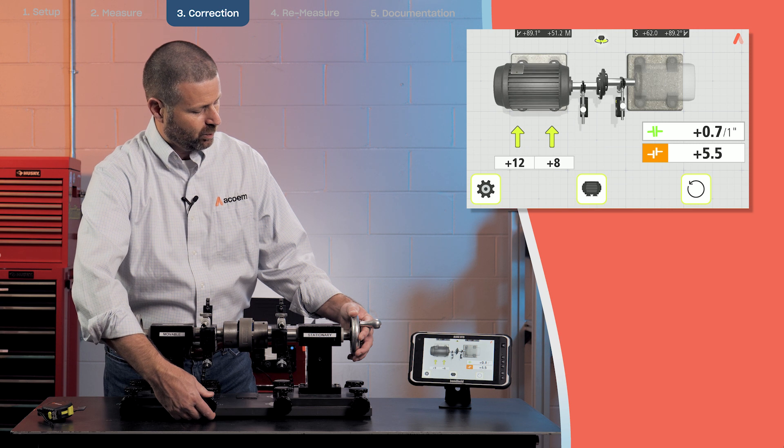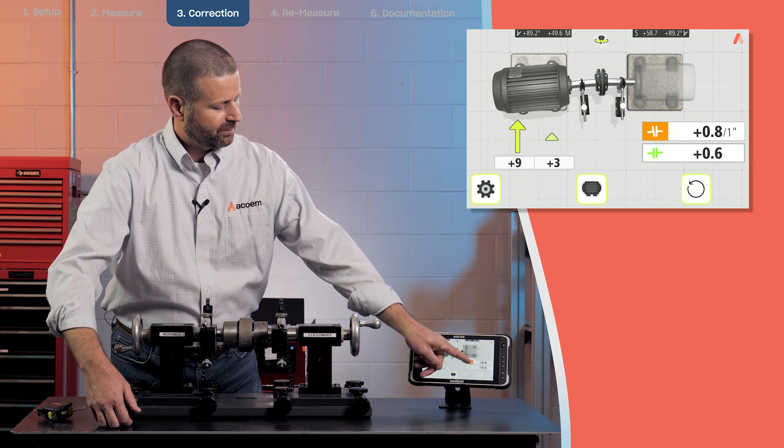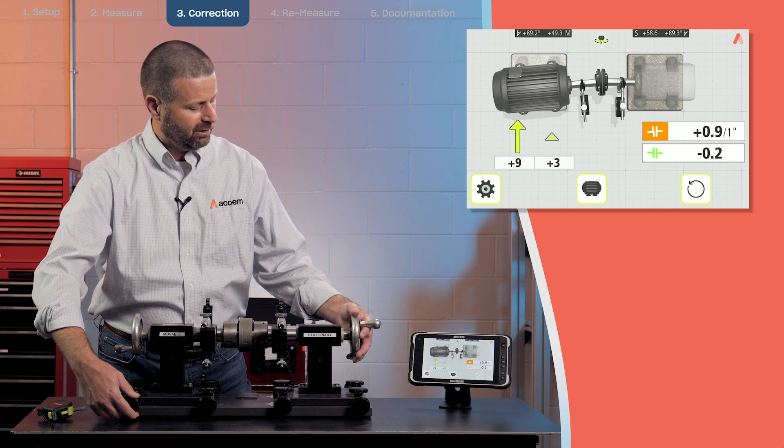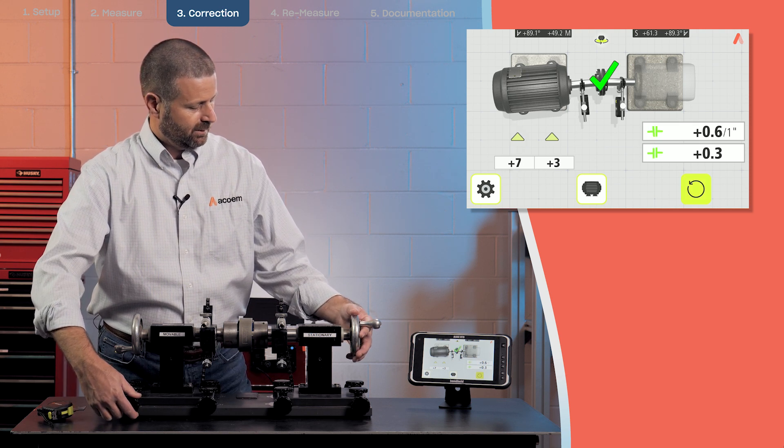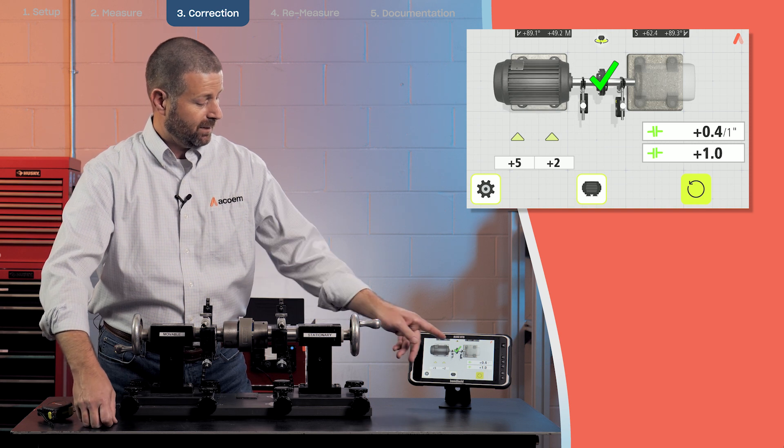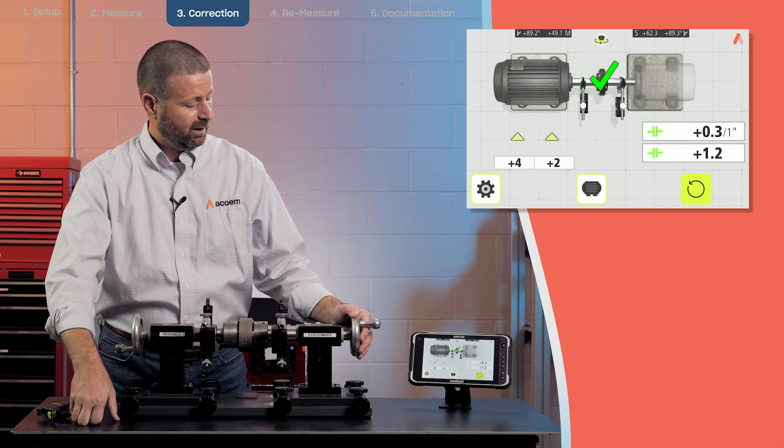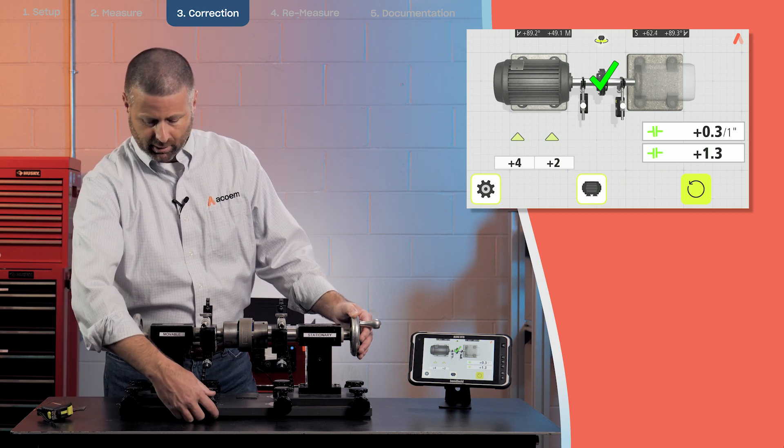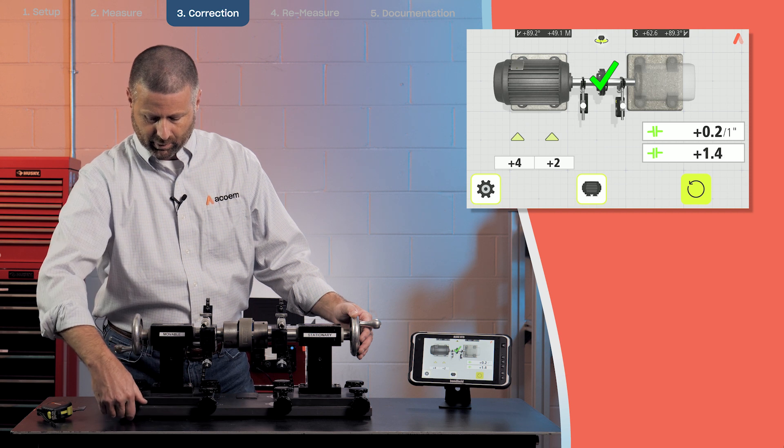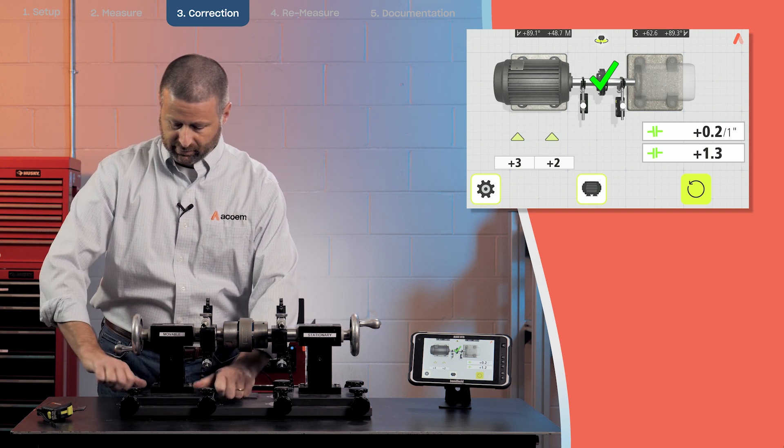And then also once you get within tolerance, you see the angle and offset values turning green. Okay, so now the check mark means that both the angle and the offset have been satisfied in terms of the tolerance. Once we do that, our alignment is complete. We're going to tighten down our bolts, but we're also going to come back and re-measure.